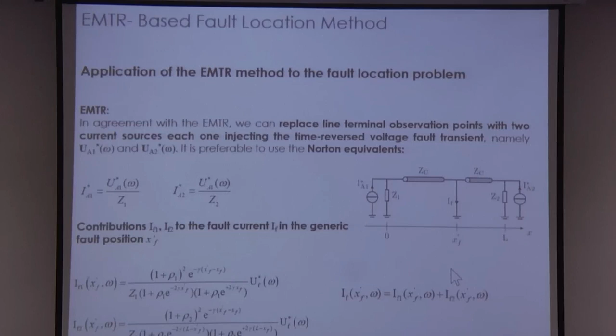What I find is the fault current at each guessed fault location. So my unknown is the guessed fault location, and I don't know where it is. What I do is move the location from the beginning to the end of the line, coordinate XF prime. For each XF prime, I find the fault current IF as a function of XF prime. From the theory and the animation I showed you, if XF prime becomes XF, I will have energy concentration. Let's see how it works.